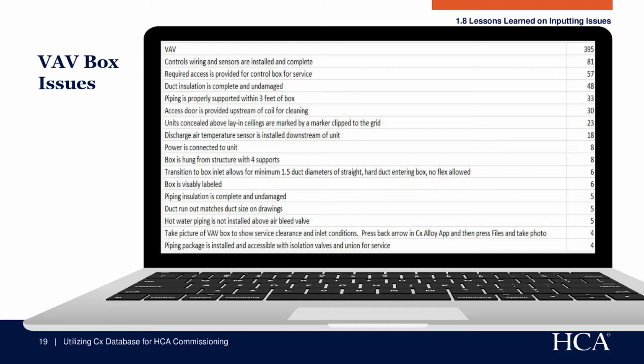In the top line, it says control wiring and sensors are installed and complete, and there are 81 issues associated with that line. That's the number one issue we have on VAV boxes, which is a shock to me. When I saw this information, it didn't make sense. I would have thought access or a straight duct run or something like that, not control wiring.